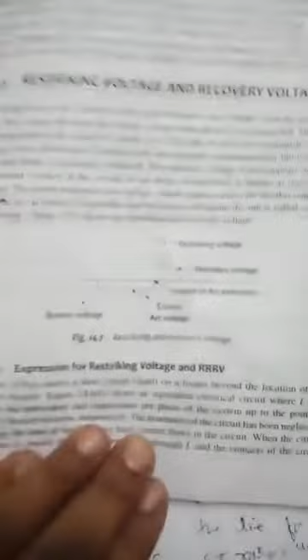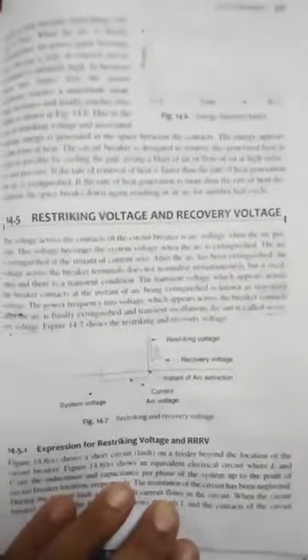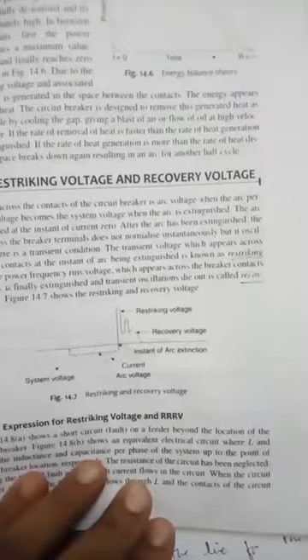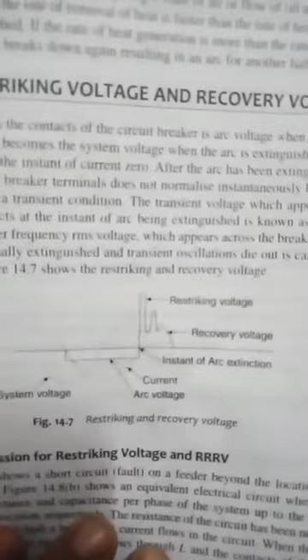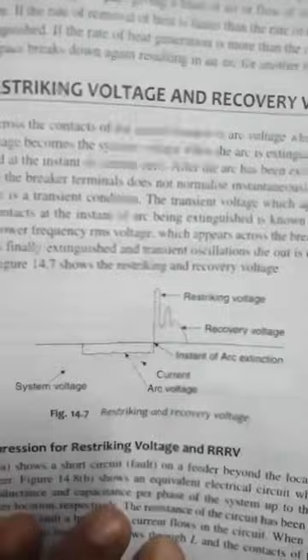Next question, define the terms recovery voltage and restriking voltage. The transient voltage which appears across the circuit breaker contacts at the instant of the arc being extinguished is known as restriking voltage. The power frequency RMS voltage which appears across the breaker contacts after the arc is finally extinguished and the transient oscillations die out is called recovery voltage. And you can draw the diagram also along with the definition.